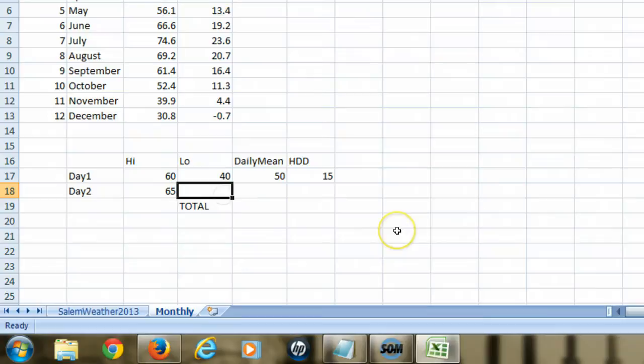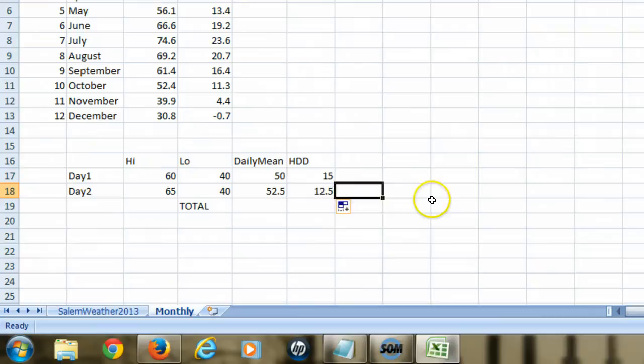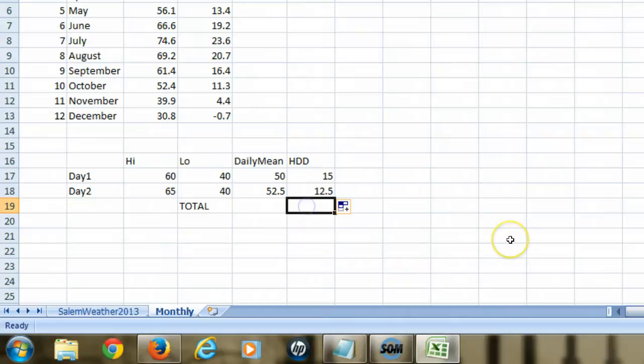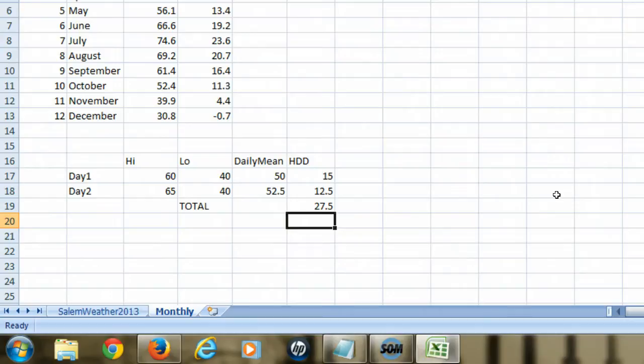Now if the next day it was 65 and 40 — so it got a little warmer — and we calculate the daily mean again, it's a slightly higher average mean, and again we calculate the heating degree days. Notice this gives a different value: 12.5 heating degree days. Adding the two values together, for those two days there were a total of 27.5 heating degree days. So you notice that heating degree days are cumulative.